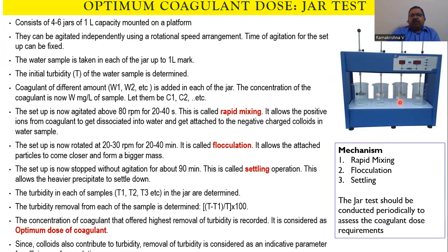Normally, on regular days, in a lean period, the water quality is almost the same, so we will not have to change the coagulant dosage much. But in the rainy season, the flood waters will come with a lot of impurities. So we need to remove most of the impurities before the water goes to the next treatment operation. Here the coagulant dose will be regularly changed.